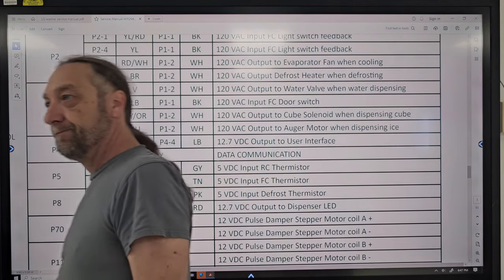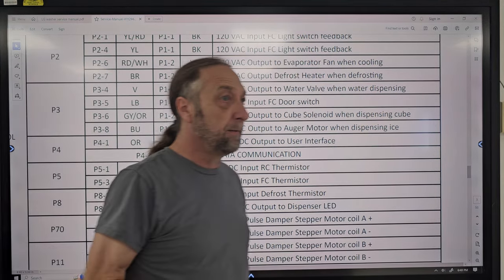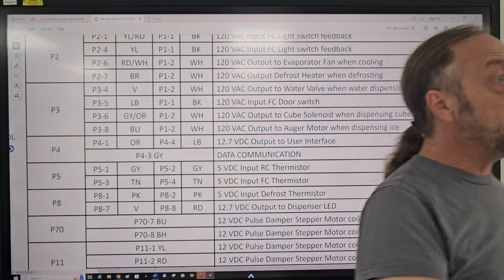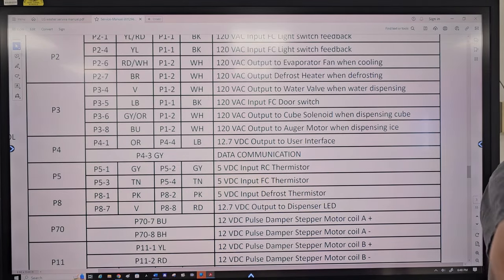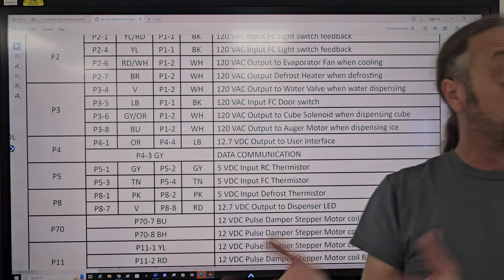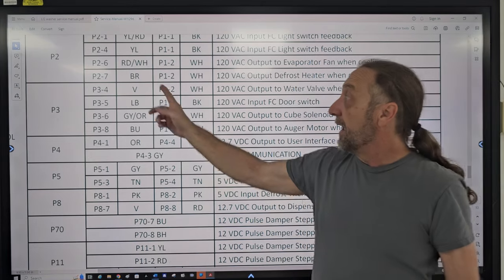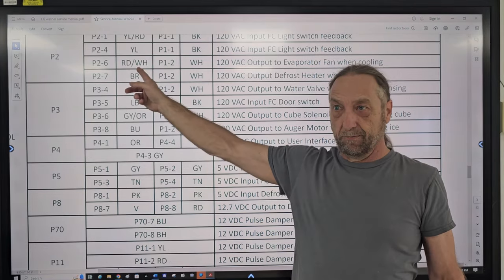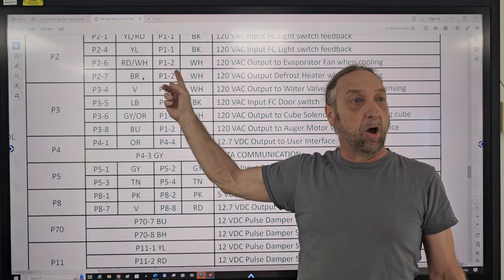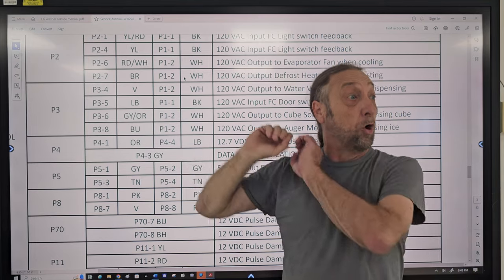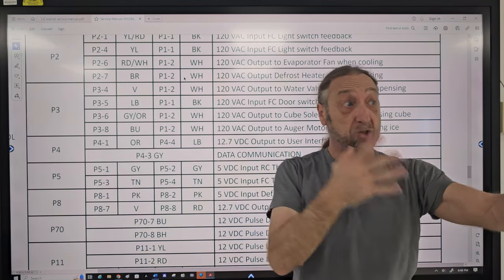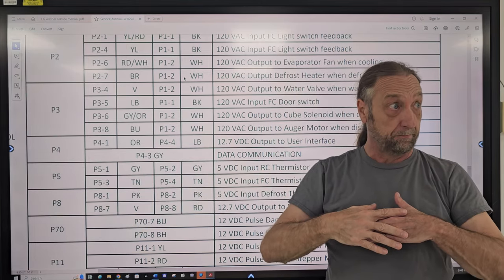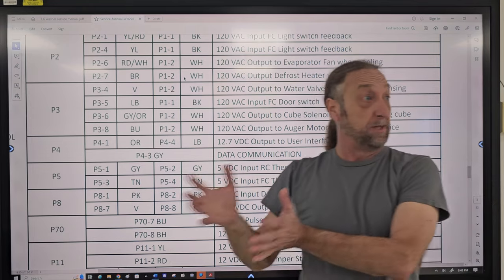Check the relay? No, the relay is what tells the fan to run, it's what sends power to the fan. So you already confirmed that you have 120 coming out of that board. Right? If I got 120 coming off the board, and these two wires are going to the fan, that means the relay is closing. So the problem is not my board.